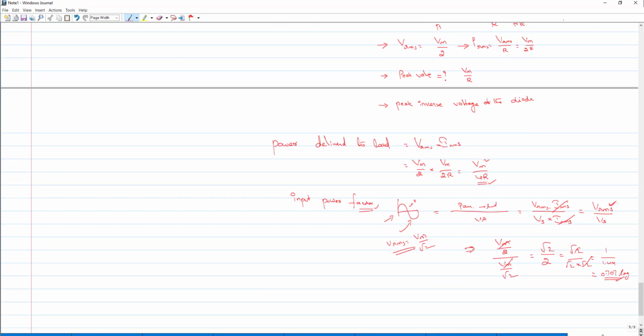So what is the important conclusion that you draw from here? Even though you are doing only rectification, when you keep this power electronic device in the AC circuit, the power factor seen at the input side is completely distorted, so we have to be very careful.